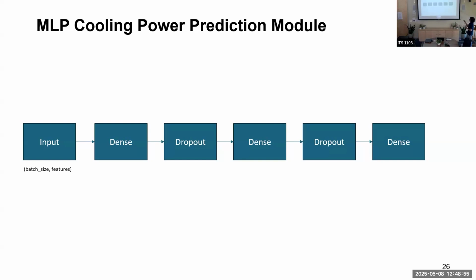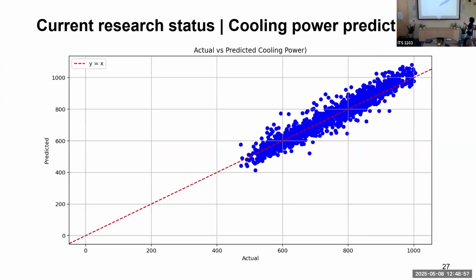This is a simple multi-layer perceptron deep learning network that learns how your control inputs, which evaporators are on, how much of the VFD step are they on, and what the outdoor temperature is, all of those inputs, and then calculates what your cooling power would be based on all these inputs, using just a data-driven prediction algorithm rather than a physics-based model. So this is how far we've got right now. We're just starting out and it's a long way to go, but that's all.